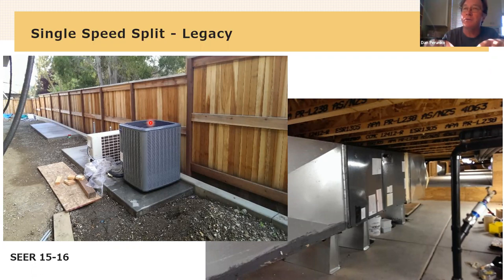And it's not super useful for you to say, okay, I'm going to get this 16 SEER machine and it's going to lower the energy consumption at my customer's house by some specific number, but it's super useful for comparison, right? If you're looking at a 16 SEER machine and a 25 SEER machine, the 25 SEER machine is significantly more efficient, right? So knowing the SEER number and comparing the different options, you always want to go for the highest SEER you can get, using it as sort of a relative scale.